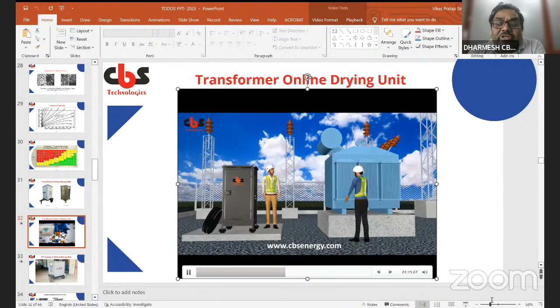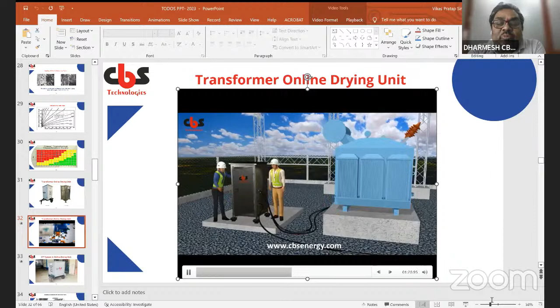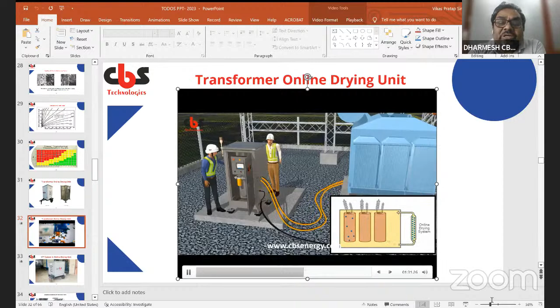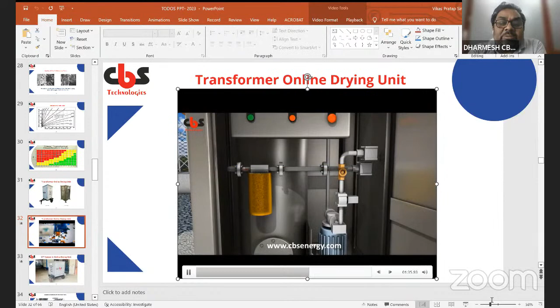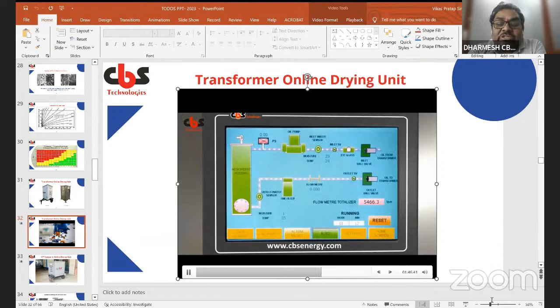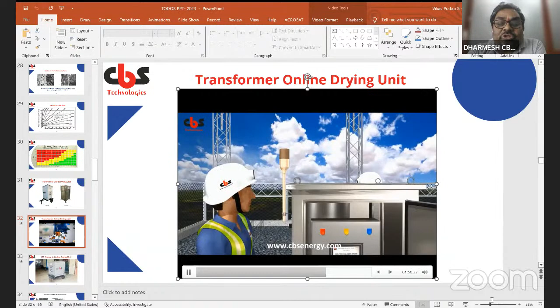There is a simple solution: a small oil dry-out system, recommended by CEA as well, which can be installed as a retrofit for all transformers, from 10 MVA to about 30 MVA. These portable machines can be taken to a single substation at 3 or 4 places. Once the ppm is maintained up to 5 ppm, the system can be taken to different small substations. For big substations, CEA has recommended putting in oil dry-out systems as a retrofit.